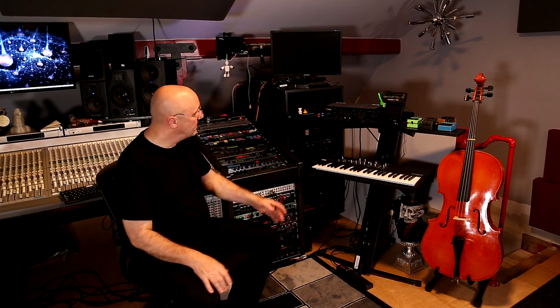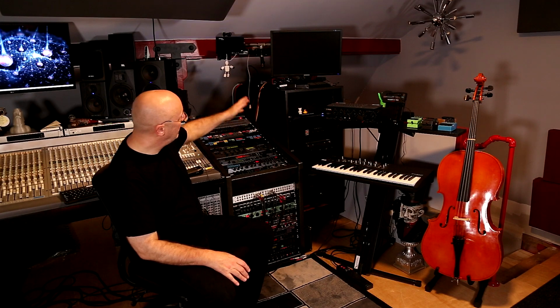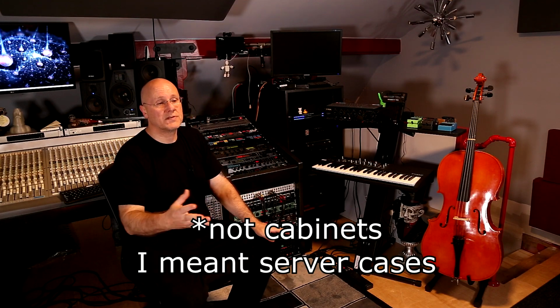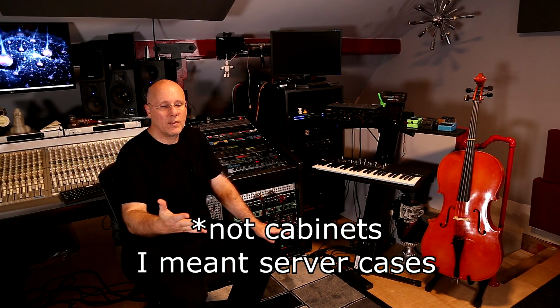So what the vented labyrinth is, it's just sort of a maze that the air can go through, and there's insulation in that pathway that stops sound from escaping. When I get the front and the back on this, basically the air for the computers, these are all in server cabinets, and server cabinets are designed to pull the cold air in the front of the cabinet and exhale the hot air out the back.